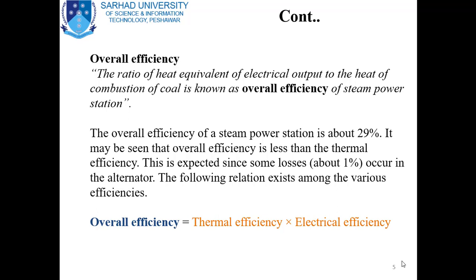The overall efficiency of the system can be defined as the ratio of output to input — specifically, as the ratio of the heat equivalent of electrical output to the heat of combustion of coal. The overall efficiency of a steam power plant is about 29%. The overall efficiency is less than the thermal efficiency because some losses of about 1% occur in the alternator.